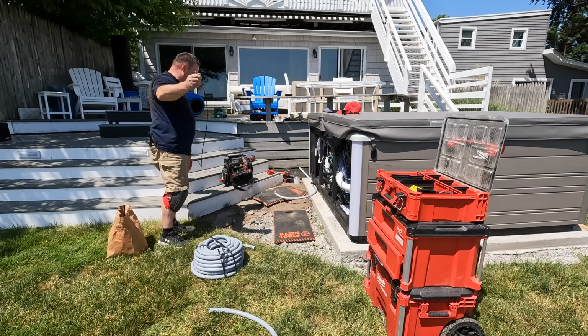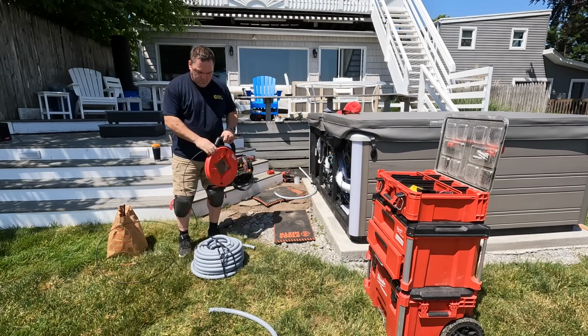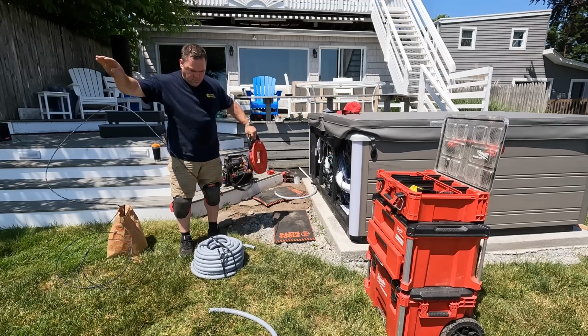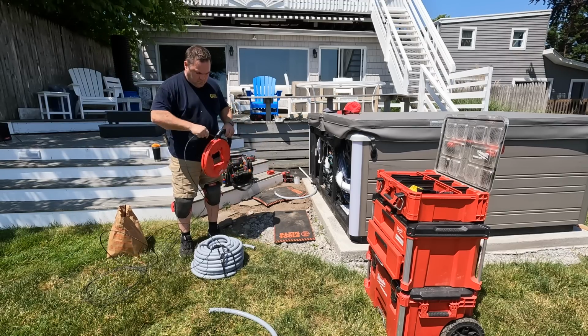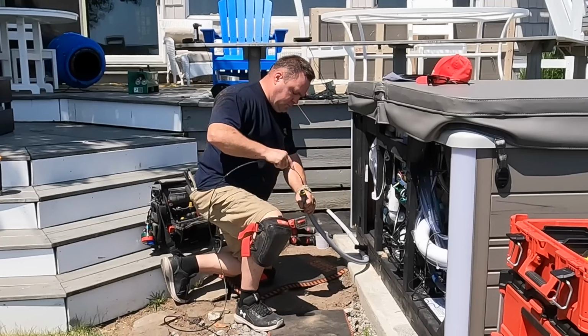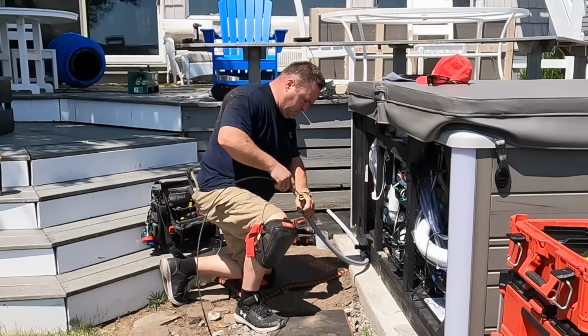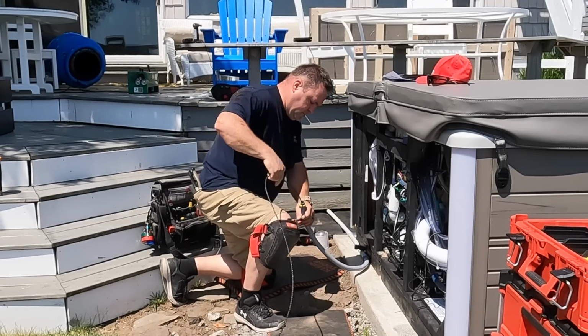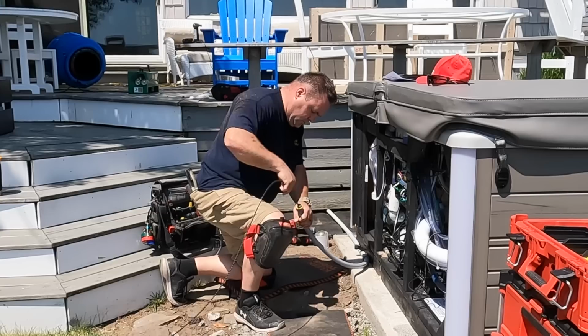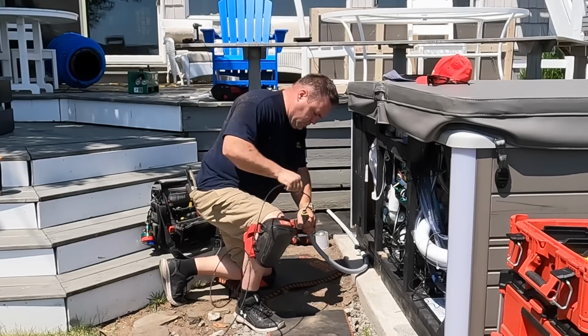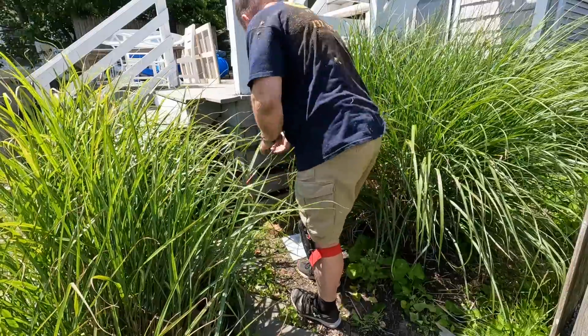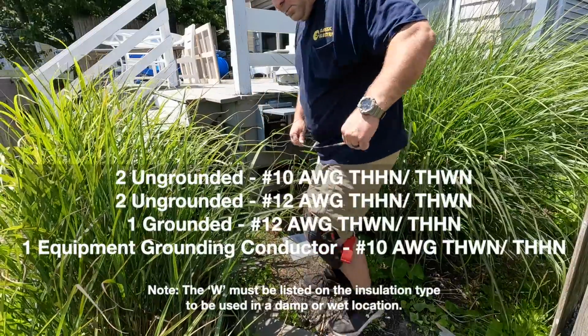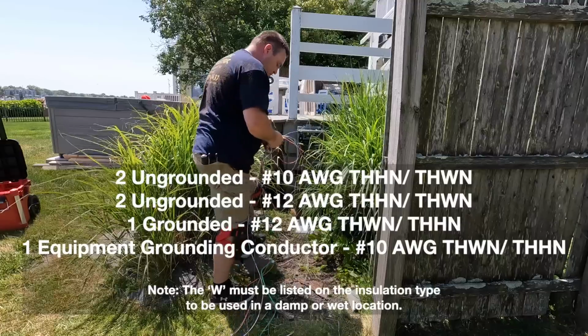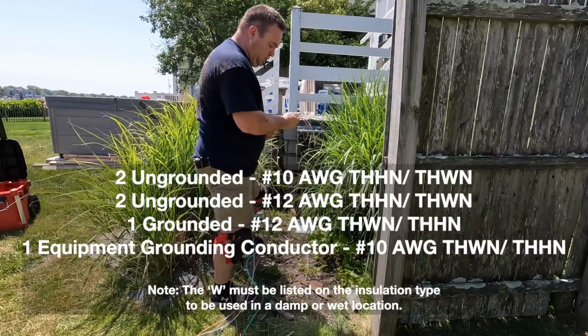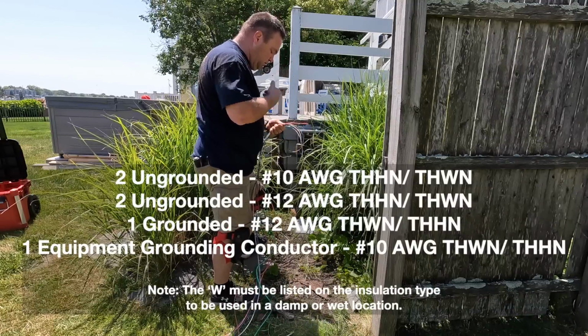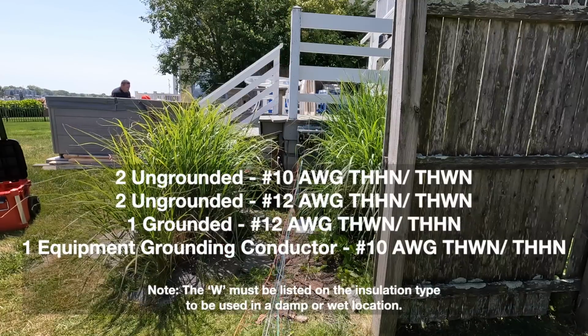The feeder then goes through the crawl space in this house all the way back to the panel in the basement. So this is my 100-foot polyester snake by Milwaukee. It's fantastic. The best part about it is it's non-conductive. So if you hit some live conductors or some live parts, you're not going to get shocked like you would using a steel fish tape. I really, really like this fish tape a lot. Obviously, it's good for pulling wires through conduits and not snaking up or fishing up walls to pull wires.